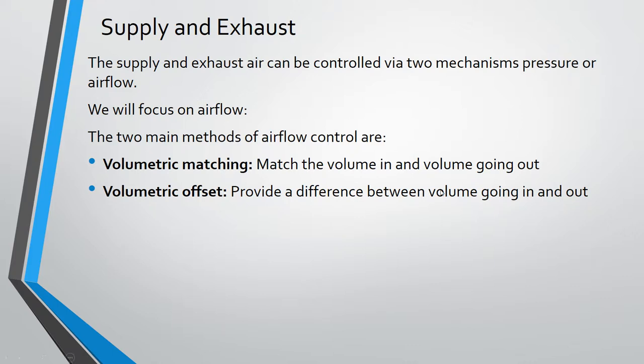You can also, on the flip side, have supply lower than exhaust. And that creates a negative scenario where you're pulling air from outside spaces in because you're exhausting more air than you're supplying in. And that air is going to come from somewhere. That would be somewhere like an infectious environment or somewhere where you don't want something in that space to leave and go to other spaces. So volumetric matching and volumetric offset, it's important to understand those two concepts.